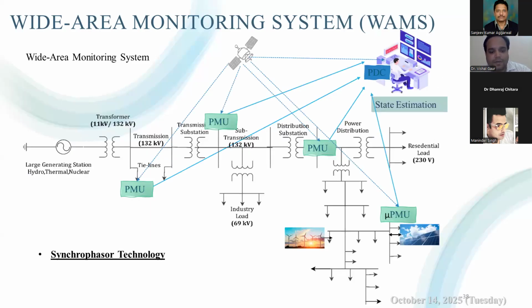This diagram shows a typical wide area monitoring system. At different points in the grid, generation, transmission, distribution, phasor measurement units are installed, and each PMU measures the voltage, current, frequency, and rate of change of frequency, and synchronizes these measurements using the GPS signal. These PMUs send their data through high-speed communication links to a phasor data concentrator, PDC, usually located at the regional center or national center. The PDC collects the data from all PMUs, aligns them based on the time stamping, and sends the synchronized information to the central level, which is the state estimation and decision support system.